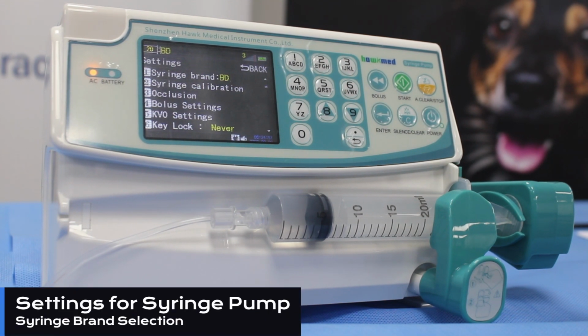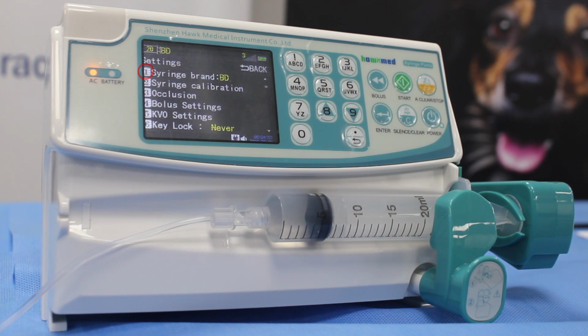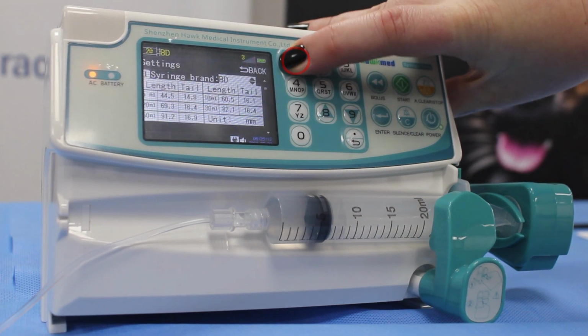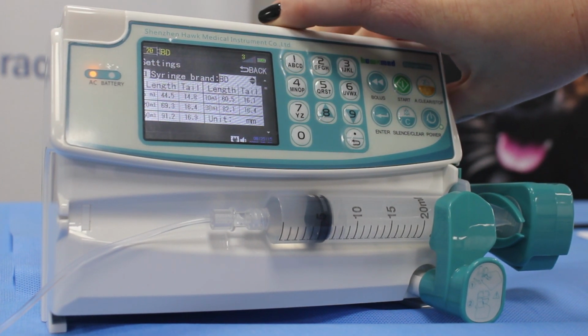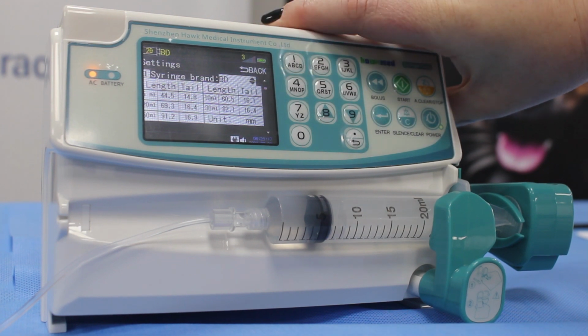Starting from the top of our settings menu, the first option available to us is syringe brand. This allows us to customize our preference for the syringe brand we would like to use with our syringe pump. The yellow highlighted writing currently displayed is showing us that BD is the preference for this pump.